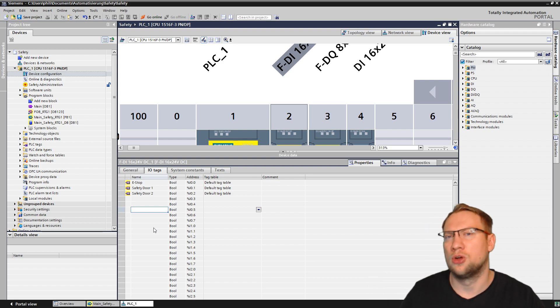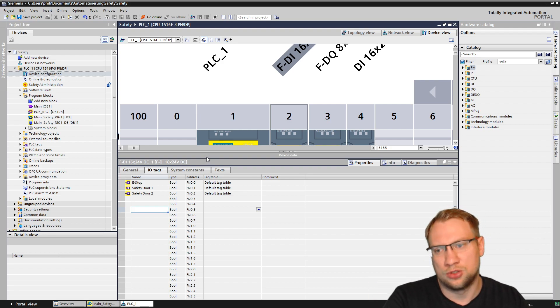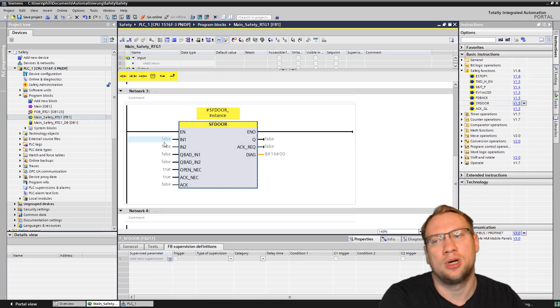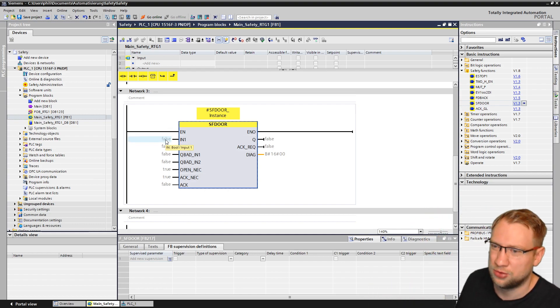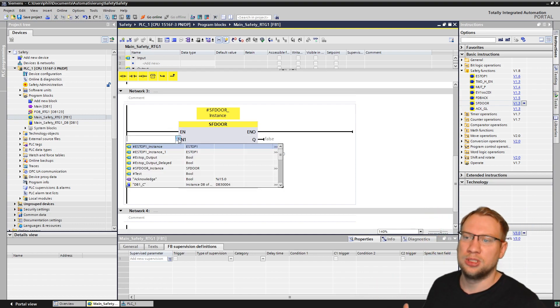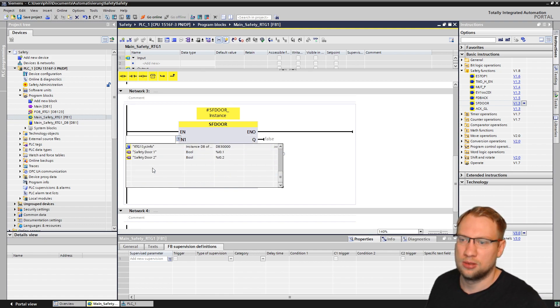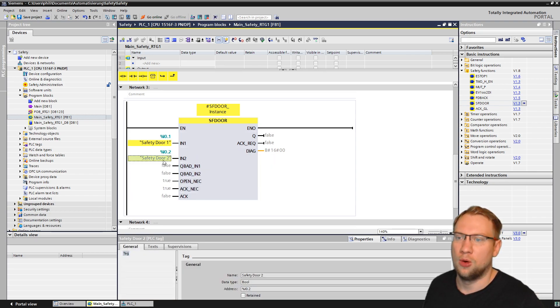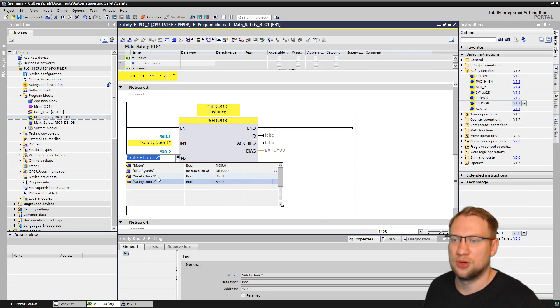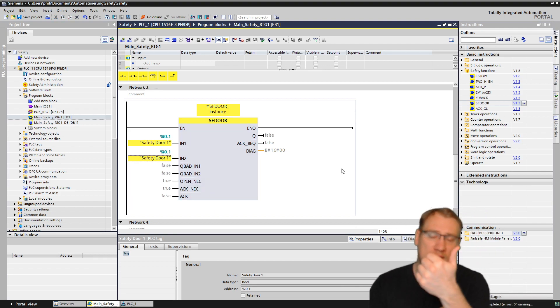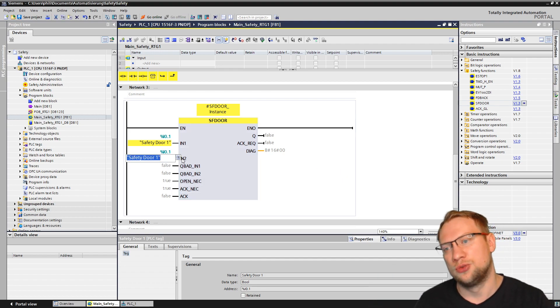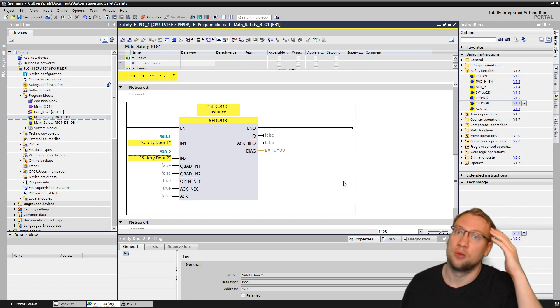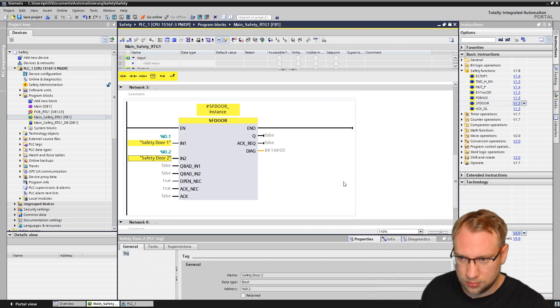We won't look at that in detail, but that's why you usually have two sensors on your door. The safety door has two inputs because the standard application uses two sensors. If you only have one sensor you can take the same sensor on both inputs — that's okay — but to comply with safety regulations, two sensors are recommended for a safety door.